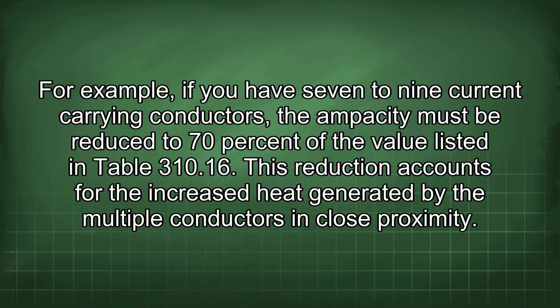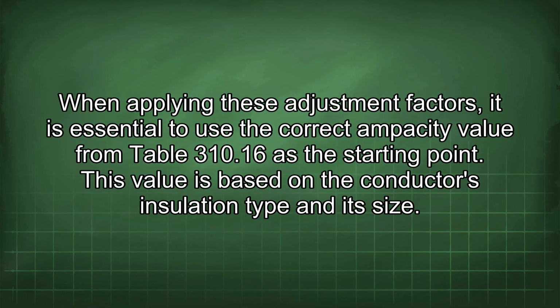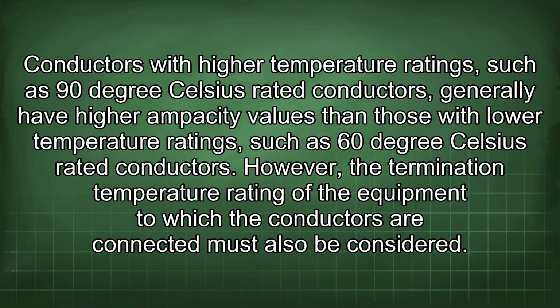if you have 7 to 9 current-carrying conductors, the ampacity must be reduced to 70% of the value listed in Table 310.16. This reduction accounts for the increased heat generated by the multiple conductors in close proximity. When applying these adjustment factors, it is essential to use the correct ampacity value from Table 310.16 as the starting point. This value is based on the conductor's insulation type and its size. Conductors with higher temperature ratings, such as 90 degrees Celsius rated conductors, generally have higher ampacity values than those with lower temperature ratings, such as 60 degrees Celsius rated conductors.